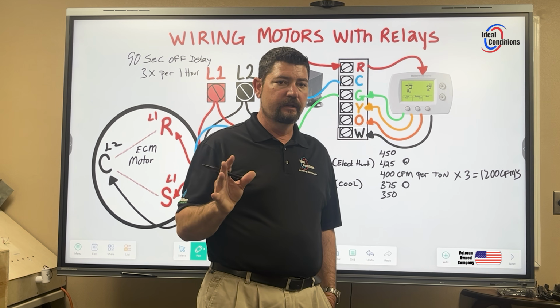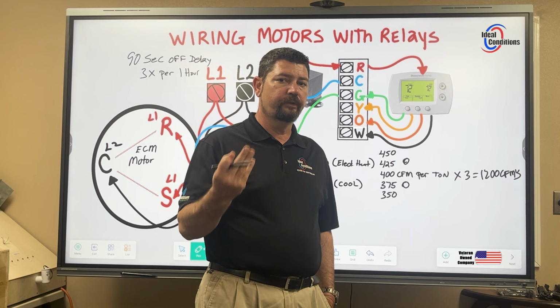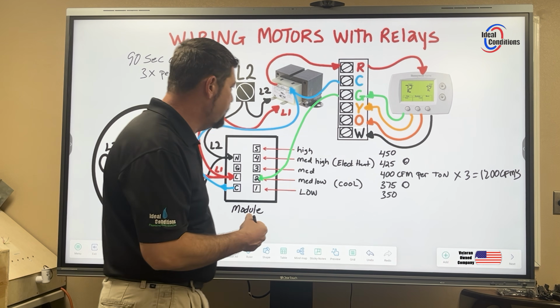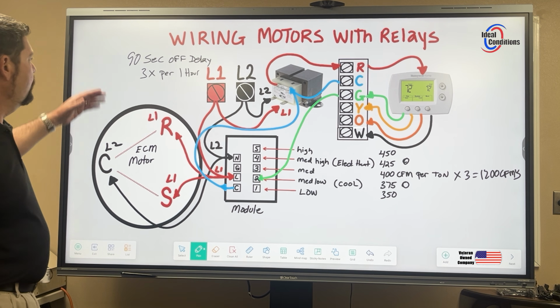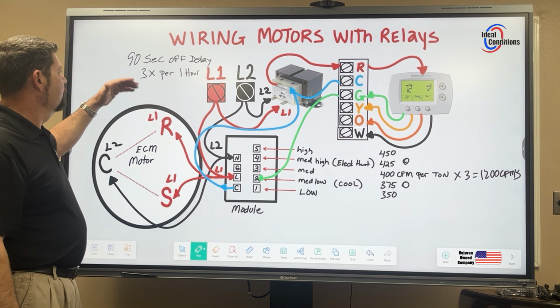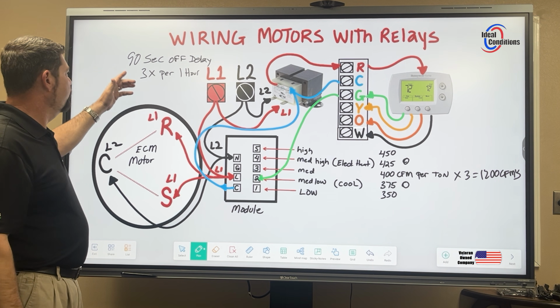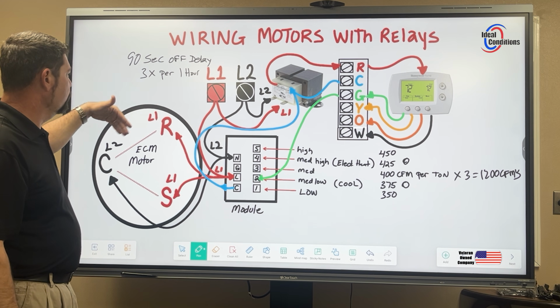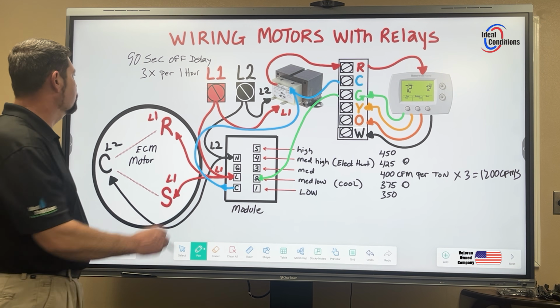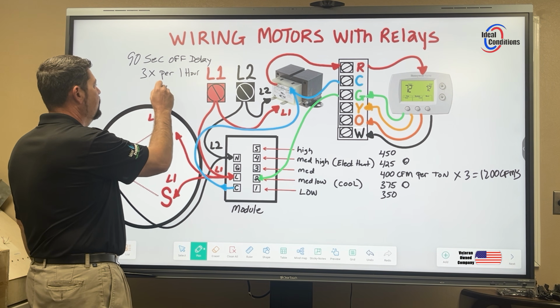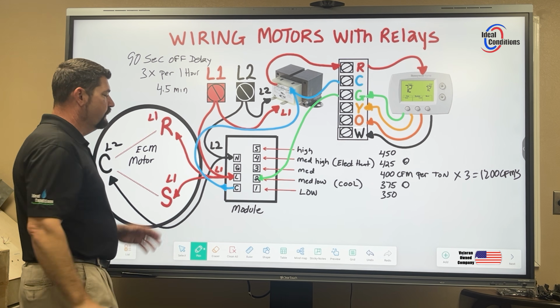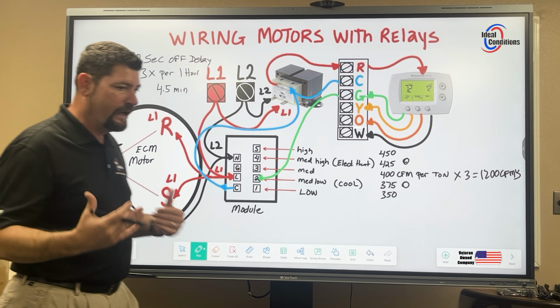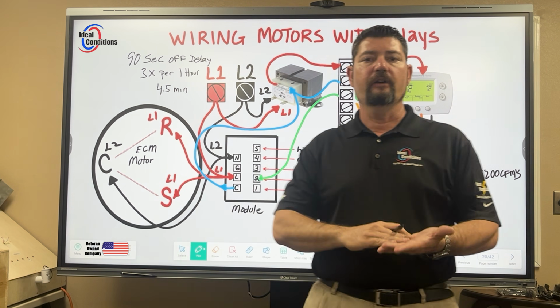And in 1 hour, that was 3 on cycles and 3 off cycles, right? So with that being said, you would say, well, it shut off 3 times, and in that 3 times that it shut off, I would just multiply 90 seconds or 1.5 minutes times 3, which comes to 4.5 minutes an hour that the blower ran past the time that the condenser shut off.